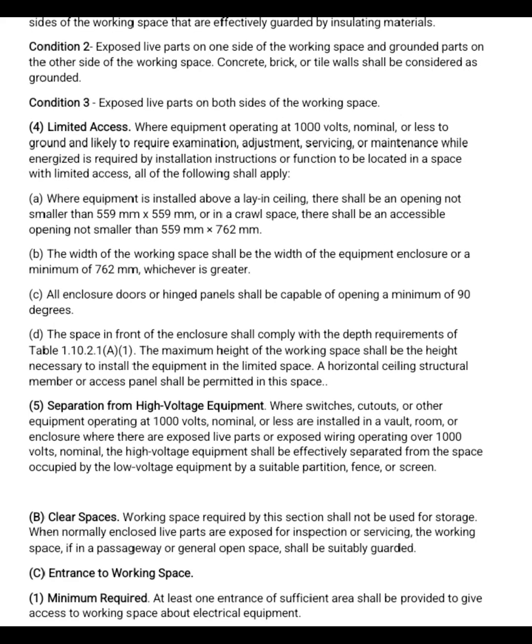Condition number 2. Exposed live parts on one side of the working space and grounded parts on the other side of the working space. Concrete, brick, or tile walls shall be considered as grounded. Condition 3. Exposed live parts on both sides of the working space. Number 4. Limited access. Where equipment operating at 1,000 volts nominal or less to ground and likely to require examination, adjustment, servicing, or maintenance while energized is required by installation instructions or function to be located in a space with limited access, all of the following shall apply.